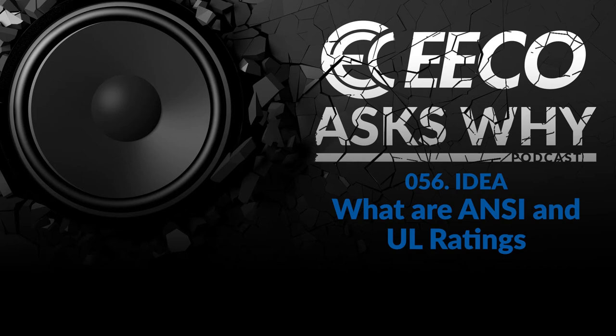Gotcha. Now, you've centered in on circuit breakers, so do ANSI ratings or UL ratings go beyond just circuit breakers and electrical distribution equipment? Yeah, absolutely. You're going to have UL ratings for a piece of switchgear, as well as ANSI ratings for a piece of switchgear as well. But it kind of starts at that circuit breaker, because at the end of the day, a piece of switchgear is just a big gray box with lots of circuit breakers in it. And that's a very simplified overlook of it, but the circuit breaker is the central part of that switchgear.